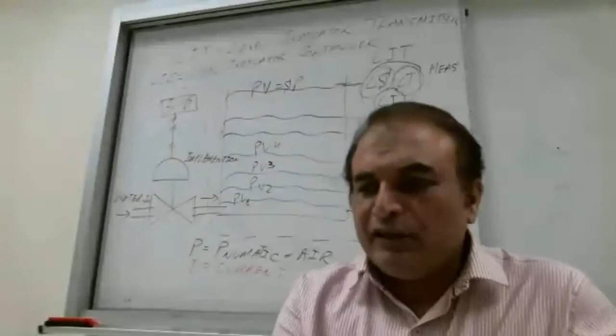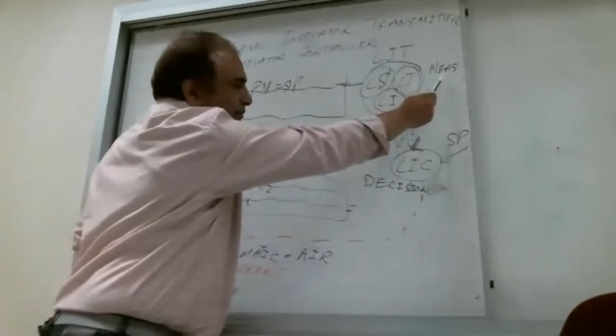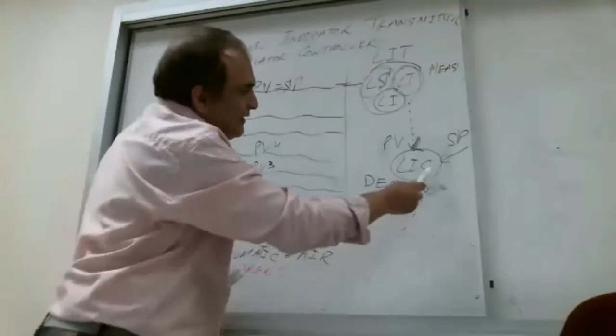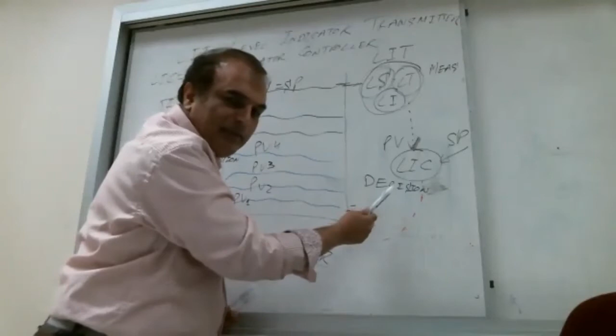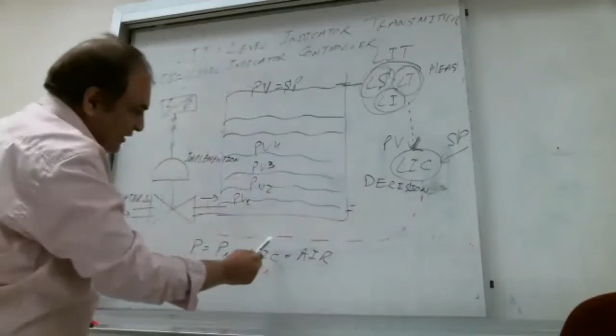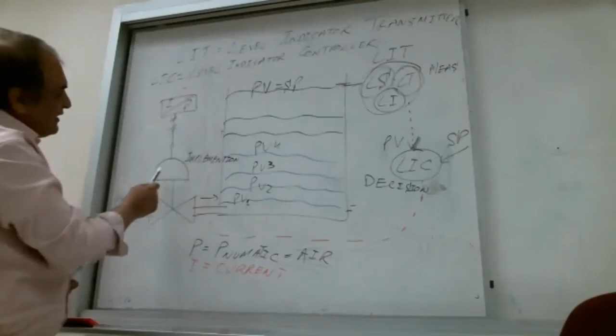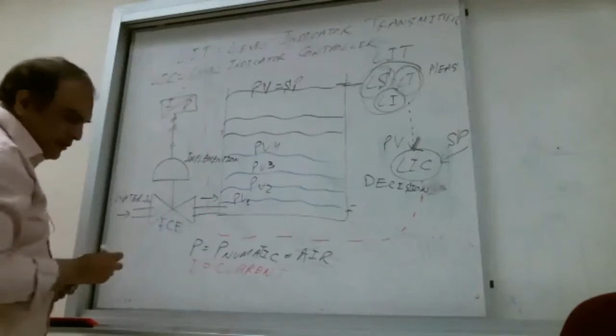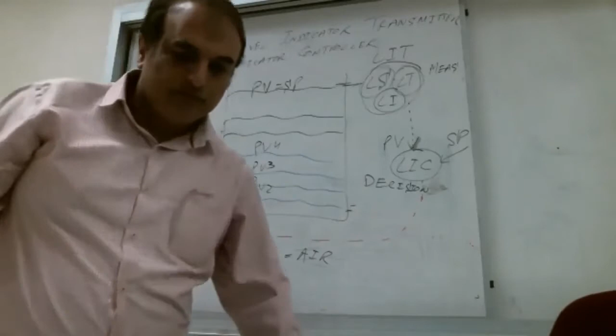Now, if you see here once again on the board, this is where the measurement is, the level indicator transmitter. And this is the level indicator controller that is doing the decision. The output of this controller we are sending to the I/P converter, and the pneumatic signal is operating this valve, that is the final control element, FCE. So three steps are there. Any question up to here?